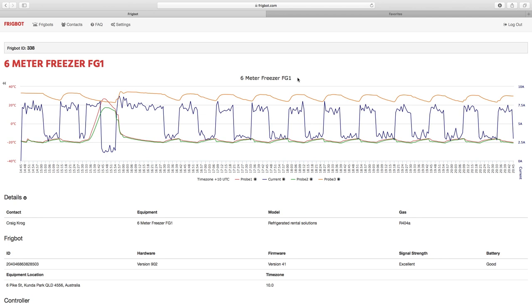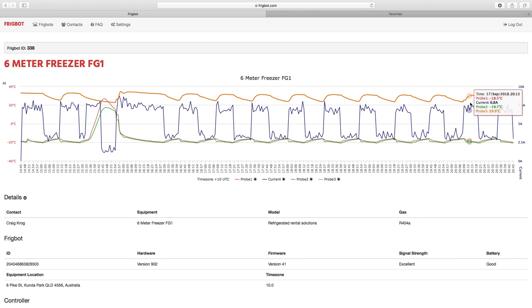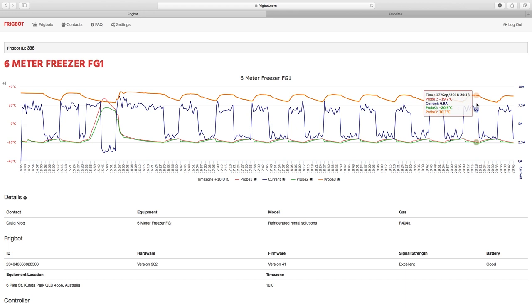This freezer is the equivalent size of a 20 foot shipping container. A 20 foot shipping container in a standard form will pull between 14 to 16 amps running during the day. So you can see by the fine tuning and the use of the correct refrigeration machinery we've been able to almost halve the electrical usage as compared to a shipping container.